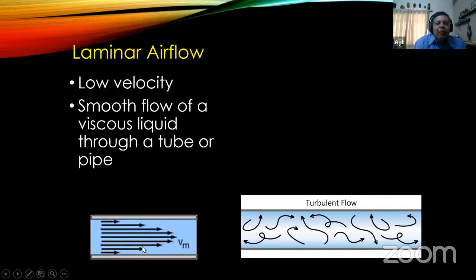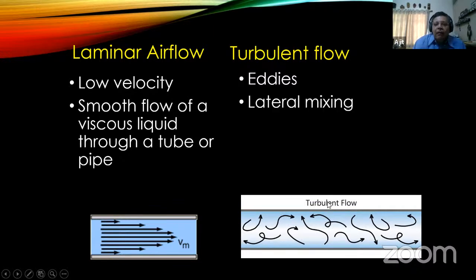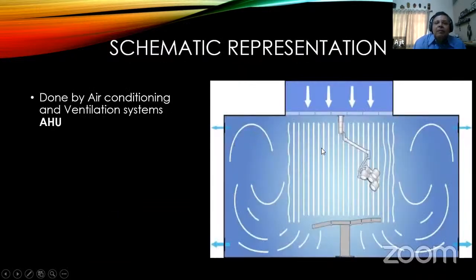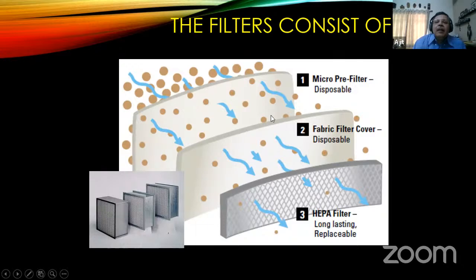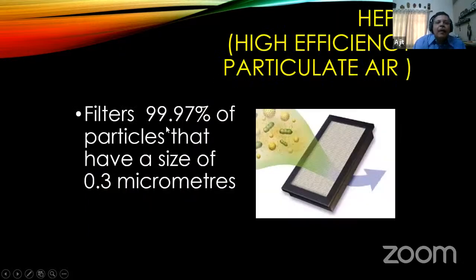So you can see sheets of air moving parallel to each other without mixing up. Whereas a turbulent airflow has got eddy currents with a lot of lateral mixing, and it's a rough airflow. This is done by the air conditioning or AHU, air handling unit, and you get a laminar airflow on the operating area. The whole of the operating area and the operating team should be covered by the laminar airflow. There should be as few obstructions to this flow as possible. The laminar airflow has 3 filters: a micro pre-filter, a fabric filter, and a HEPA filter. Now, HEPA filter is important because it filters 99.97% of particles that have a size of 0.3 micrometers. So, except for the viruses, everything else is kept out.